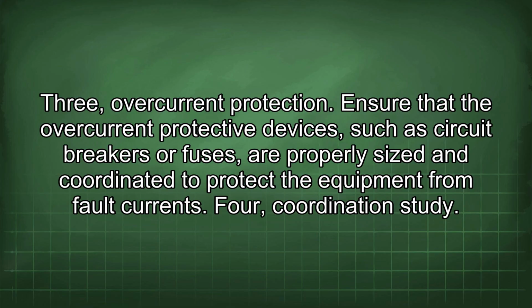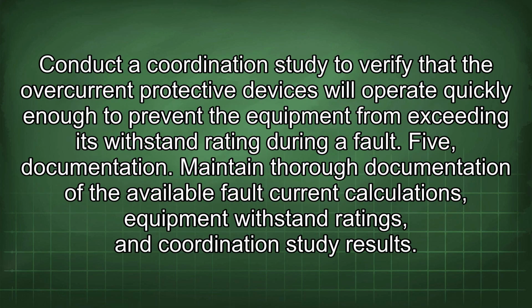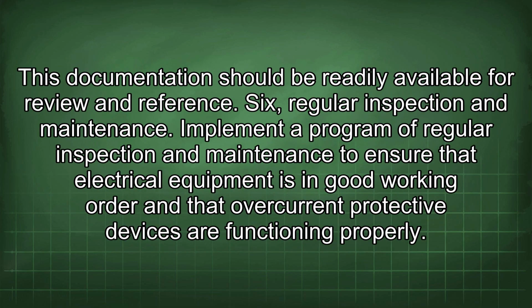4. Coordination study. Conduct a coordination study to verify that the overcurrent protective devices will operate quickly enough to prevent the equipment from exceeding its withstand rating during a fault. 5. Documentation. Maintain thorough documentation of the available fault current calculations, equipment withstand ratings, and coordination study results. This documentation should be readily available for review and reference. 6. Regular inspection and maintenance. Implement a program of regular inspection and maintenance to ensure that electrical equipment is in good working order and that overcurrent protective devices are functioning properly.